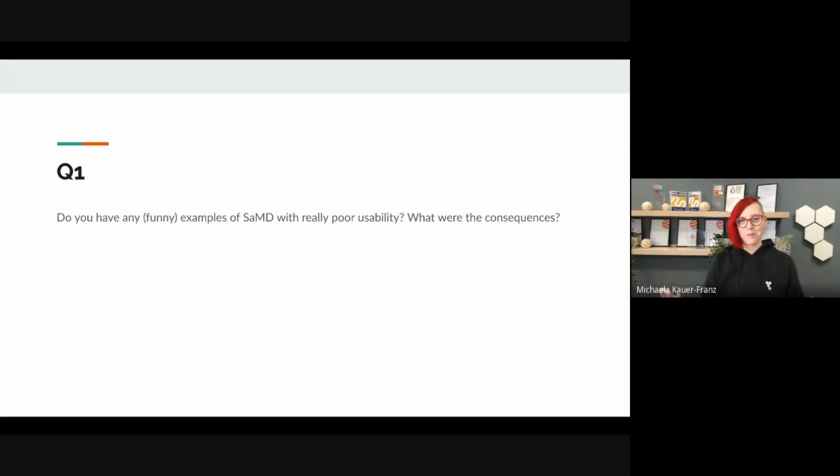But now it comes to the funny or sad part, depending on how you interpret it. So probably if you're a manufacturer, it's a good thing, because the usability awareness of the notified bodies is very low here. They were able to put together a rationale why it's still fine. So it doesn't have any consequences because they performed the summative evaluation. And they were able to work through it.